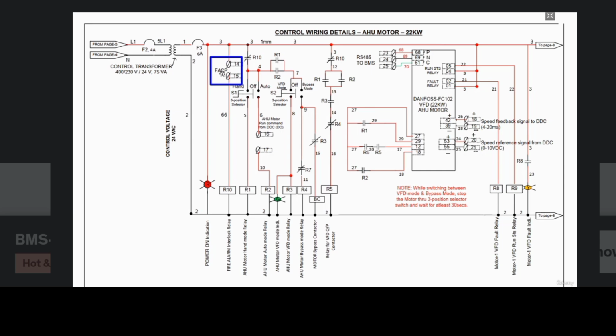This is a fire alarm interlock signal, which shall be terminated on terminal number 14 and 15. This signal shall be normally closed. So in case of fire alarm, this contact will be opened and the MCC panel will shut down the AHU. Then here we have the AHU motor run command from the DDC. This command signal shall be terminated on terminal numbers 16 and 17.